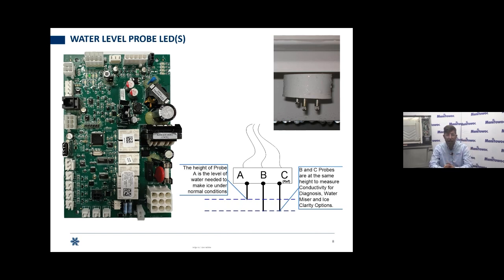But this is a good graphic all the same, not just because it's more visually appealing to see 1 light over 2, but what you could see at that point is, hey, the high probe satisfies, but the low probe doesn't. That's going to let you know there's something going on with that water probe, or maybe the connection on the board going on there. You can troubleshoot your water system diagnostics in accordance with your tech handbook to see what's going on, tell the board what you want to know by doing some jumpers, and get the lights to light up. If they do, you know it's going to be the probe. You could ohm out that probe as well, but ideally, with a proper functioning ice machine, proper functioning water probe, filling with water, I would expect that the low probe would satisfy first, then the high probe would satisfy next. But if you did see this, you could see water faults in your future.